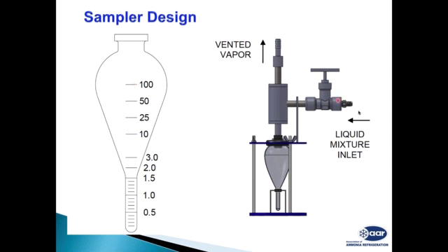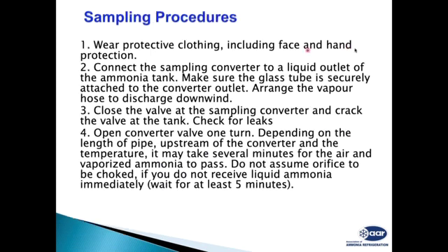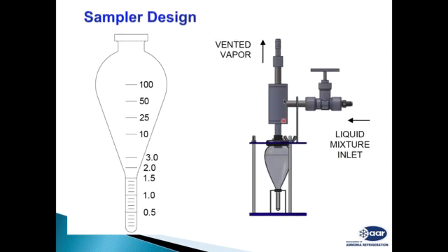Once we connect this, this is the procedure. Wear protective clothing, face shield, hand gloves. Very important: make sure you have all the PPE available before taking any sample. Connect the sampling converter to the liquid ammonia system, like the low pressure vessel ammonia liquid line, the pump liquid outlet, and the oil drain valves in the gravity feed system. Make sure this glass is secured, connect it here, and take a sample.